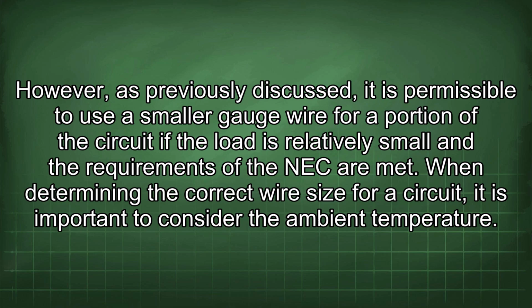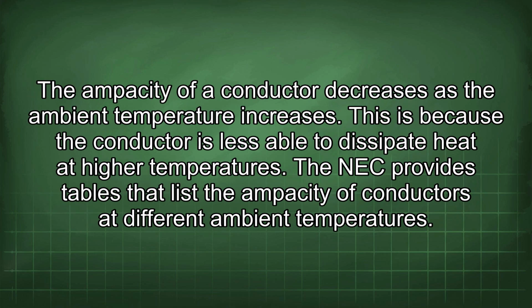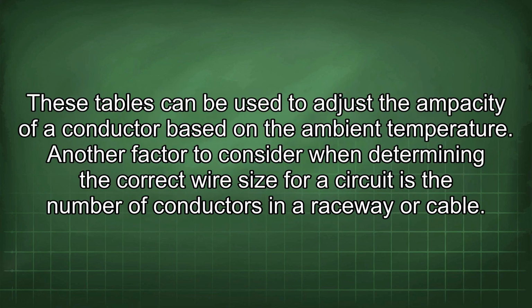When determining the correct wire size for a circuit, it is important to consider the ambient temperature. The ampacity of a conductor decreases as the ambient temperature increases. This is because the conductor is less able to dissipate heat at higher temperatures. The NEC provides tables that list the ampacity of conductors at different ambient temperatures. These tables can be used to adjust the ampacity of a conductor based on the ambient temperature.